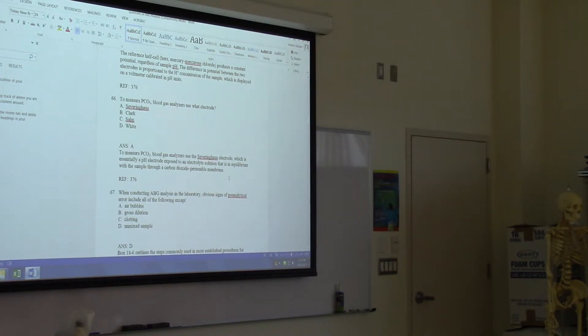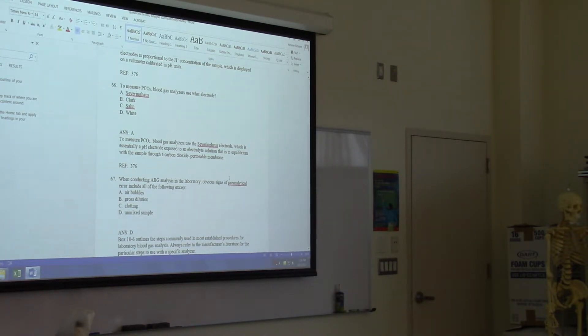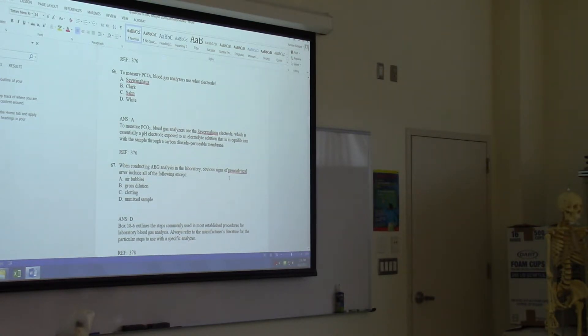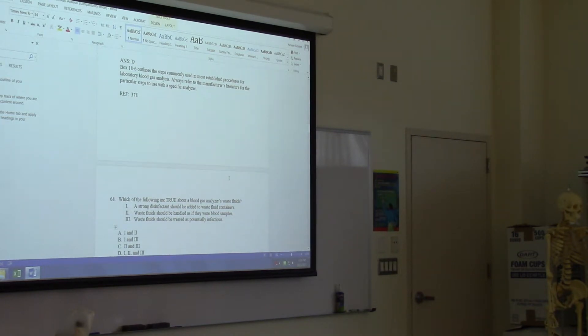It says refer to the manufacturer's literature. Which of the following are true about a blood gas analyzer's waste fluids? A strong disinfectant should be added to the waste fluid containers. Waste fluids should be handled as if they were blood samples. Waste fluids should be treated as potentially infectious. All of them, D.